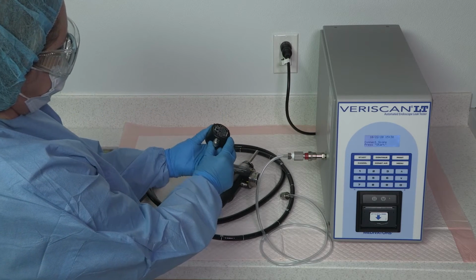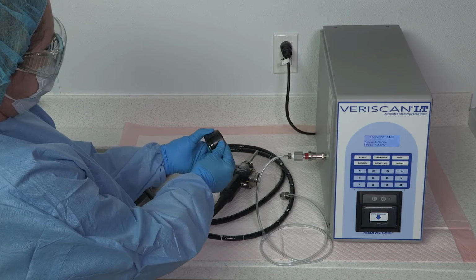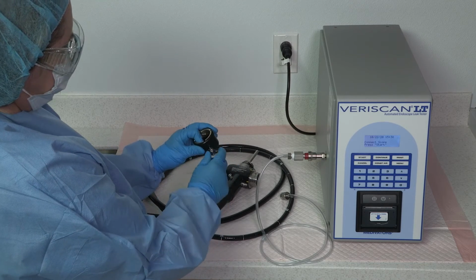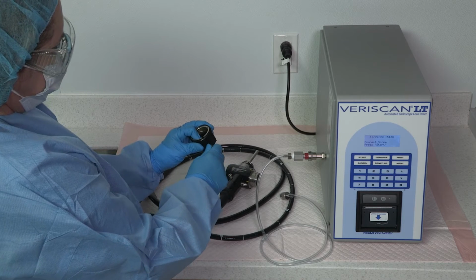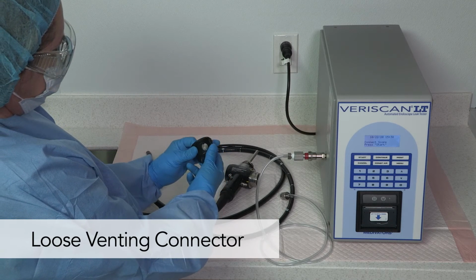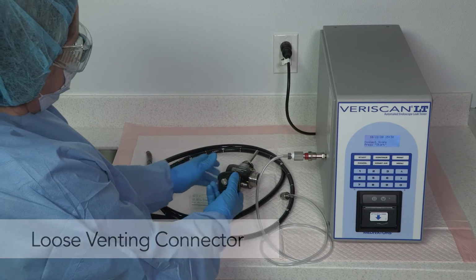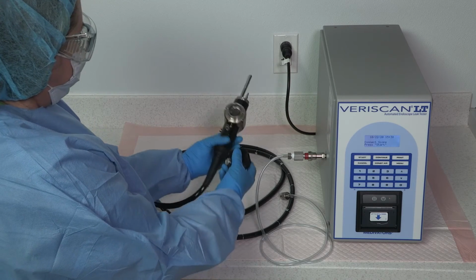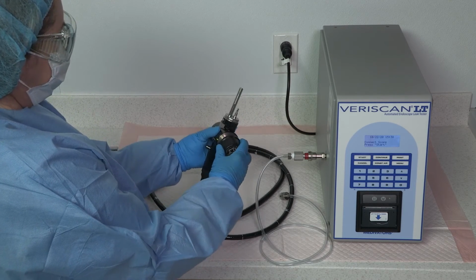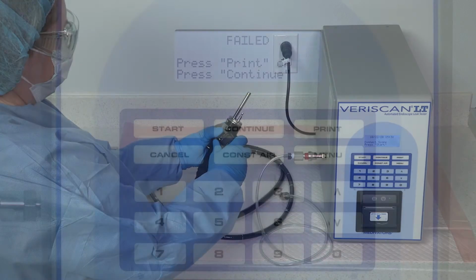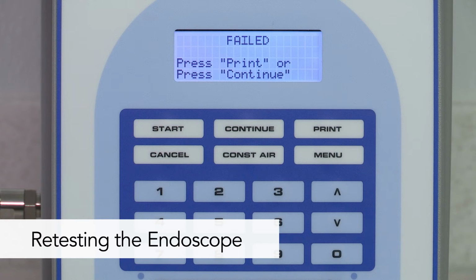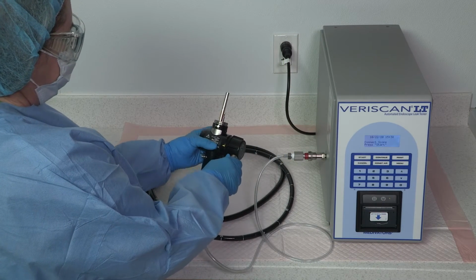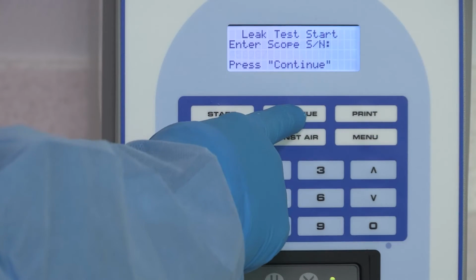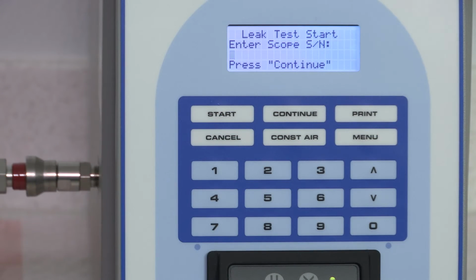If the venting connector on the endoscope or the water-resistant cap is loose, air can escape and cause a false fail leak test result. Inspect the venting connector on the endoscope or on the water-resistant cap for damage or signs of being loose. Send the endoscope out for repair or replace the water-resistant cap if worn or damaged. In the event of a failed test result, the endoscope leak test should be repeated. Reattach the endoscope and Quick Connect tubing. Press Continue to remove the failed endoscope message and prepare the VERISCAN Leak Tester for the next test.